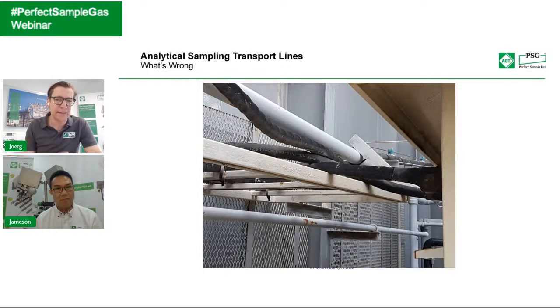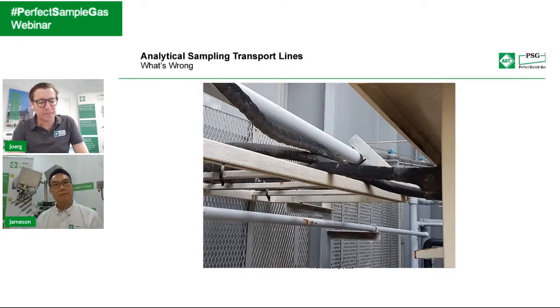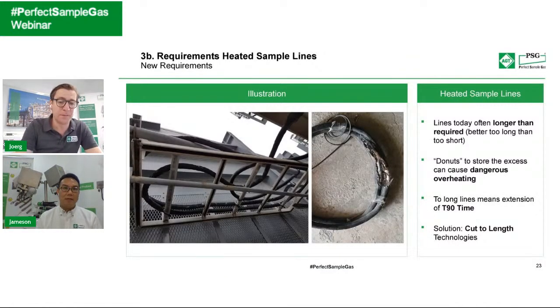I mean, when we talk about quick fix here in the CEM system, I think the layout and the dimension of the PTFE tubes inside also have an effect on the response times, obviously. But if you once decided to go for 8 millimeter outside, 1 millimeter thickness with a 6 millimeter inside tube, it's pretty hard to change this after it is installed, right? And other effects we already touched on, such as memory effects or any other effects which might come from the line, you will probably not see when you choose a high quality PTFE.